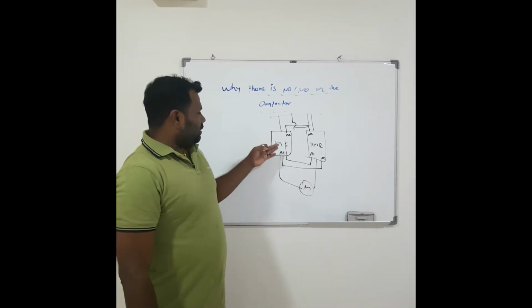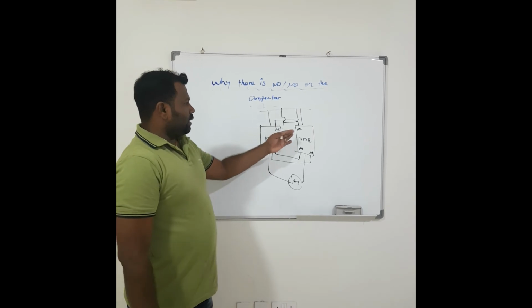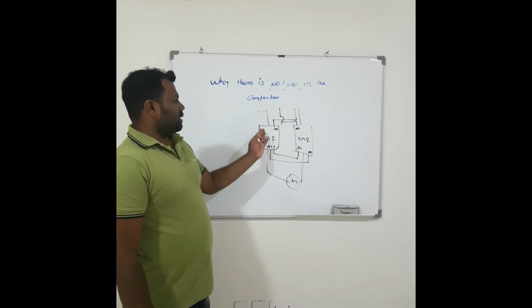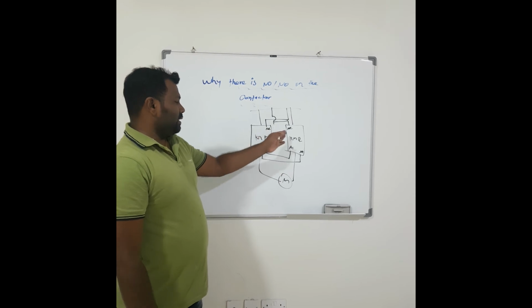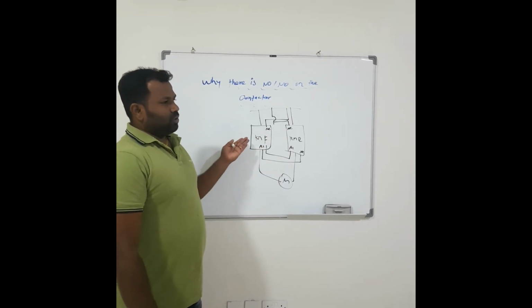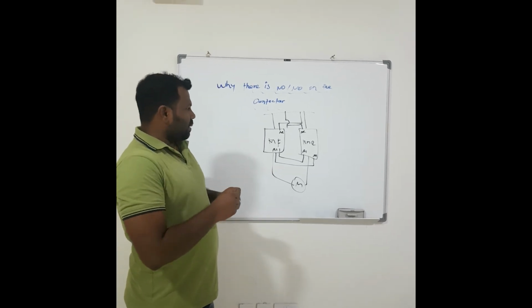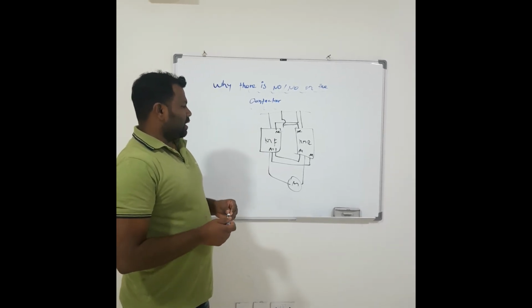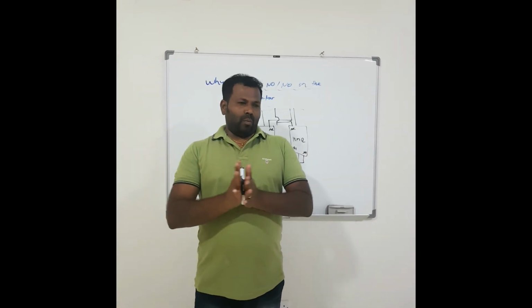Okay. Once this contactor is energized, this NC will open, so it is not possible to close this contactor at the same time. And likewise, once this contactor is energized, this contactor coil is connected with this NC. So this contactor cannot be closed through this control supply because it is opened through the NC contact. Okay. So this NC contact is used for interlock purposes also.